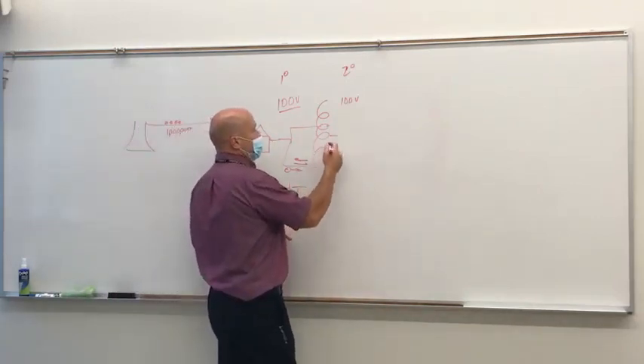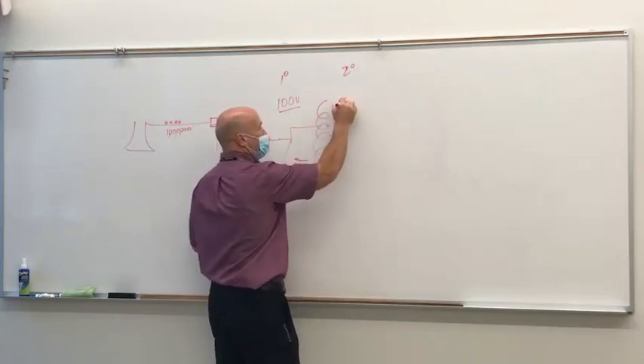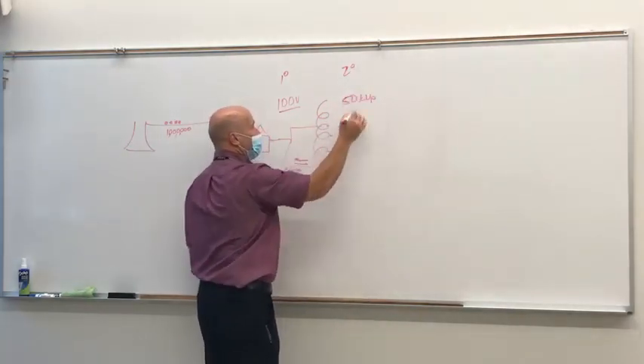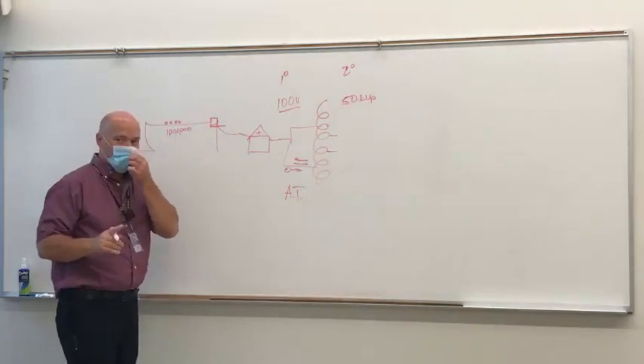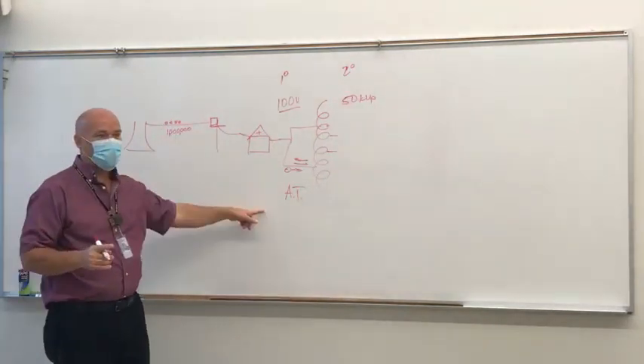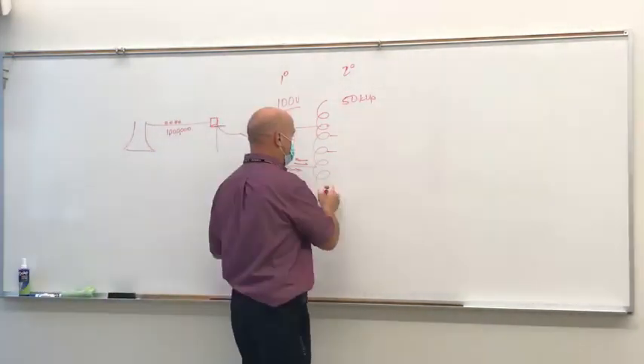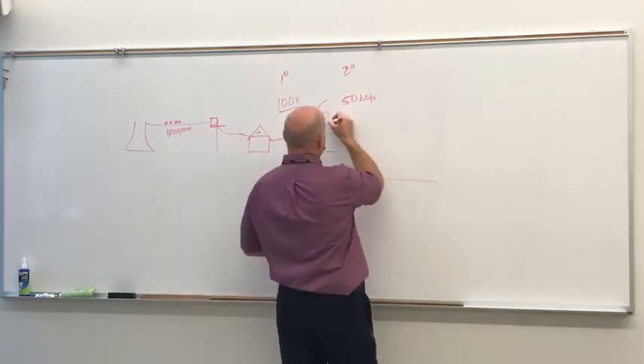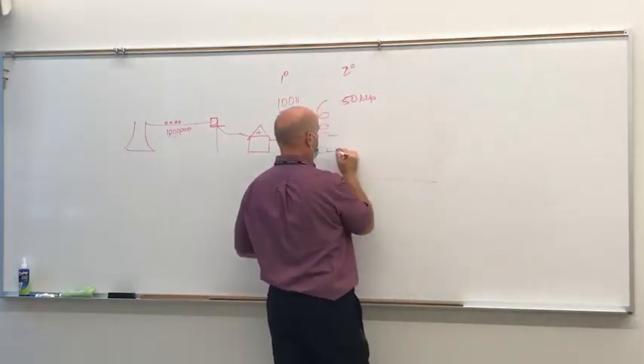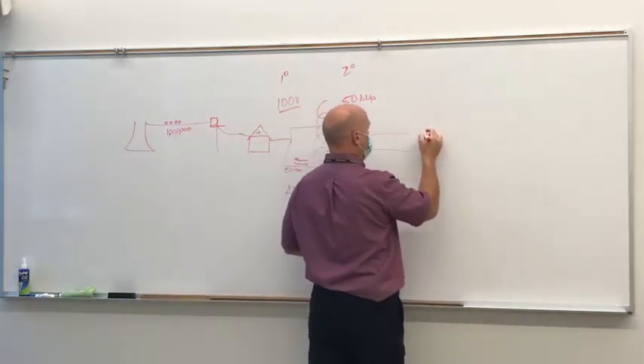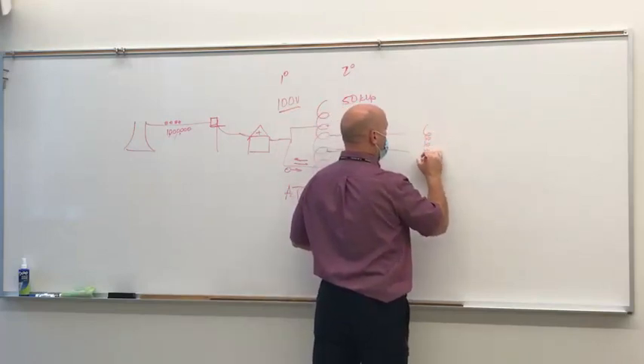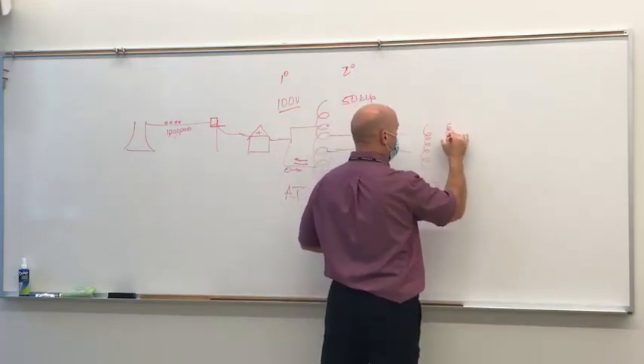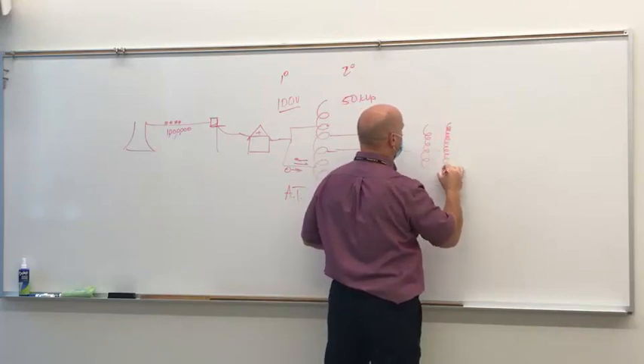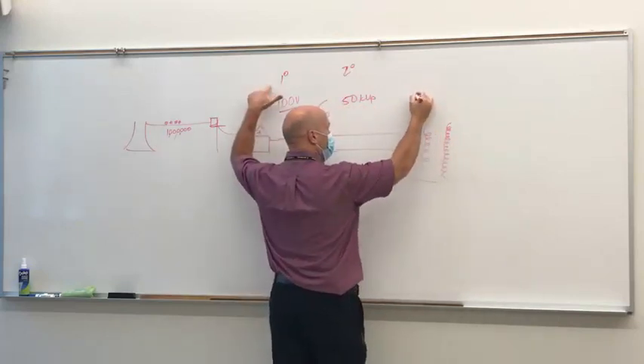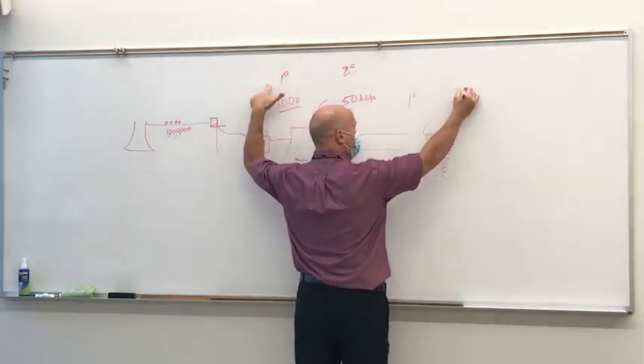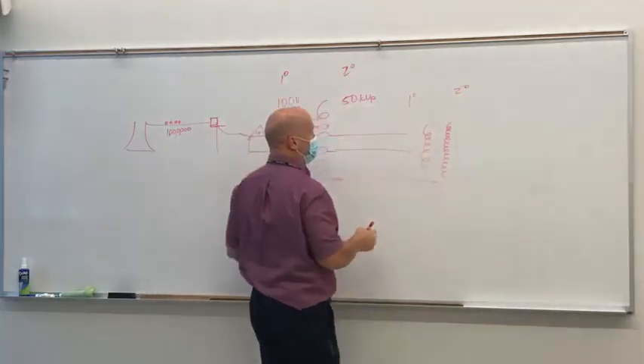So we decrease our voltage, we're shooting for 50 kVp is what we're eventually going to have. But we don't have kVp yet. This is our kVp selector, but we don't have kVp until it comes out of this, and goes into another one where our turns ratio is set, and we have more turns on the secondary side than on the primary side.